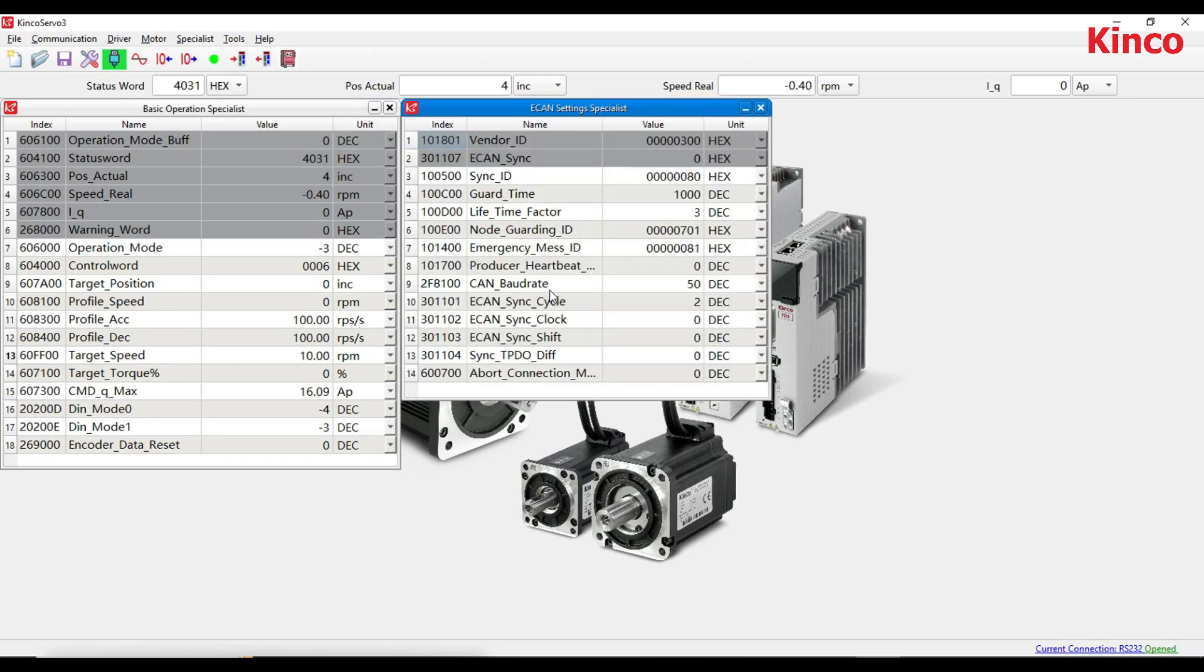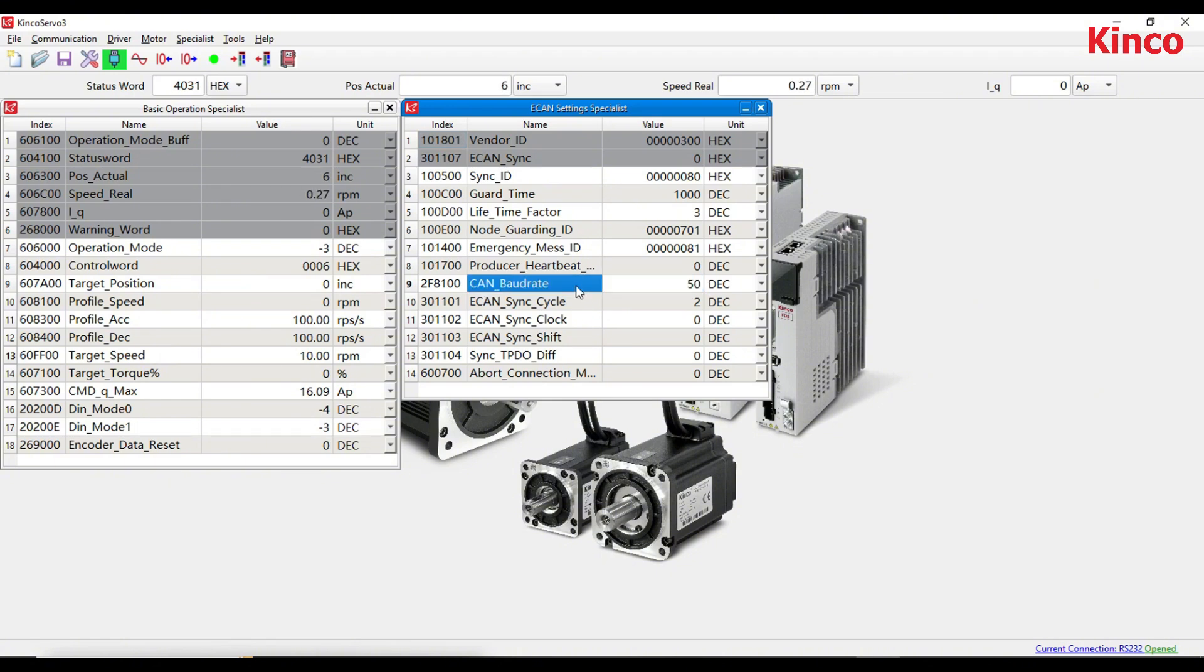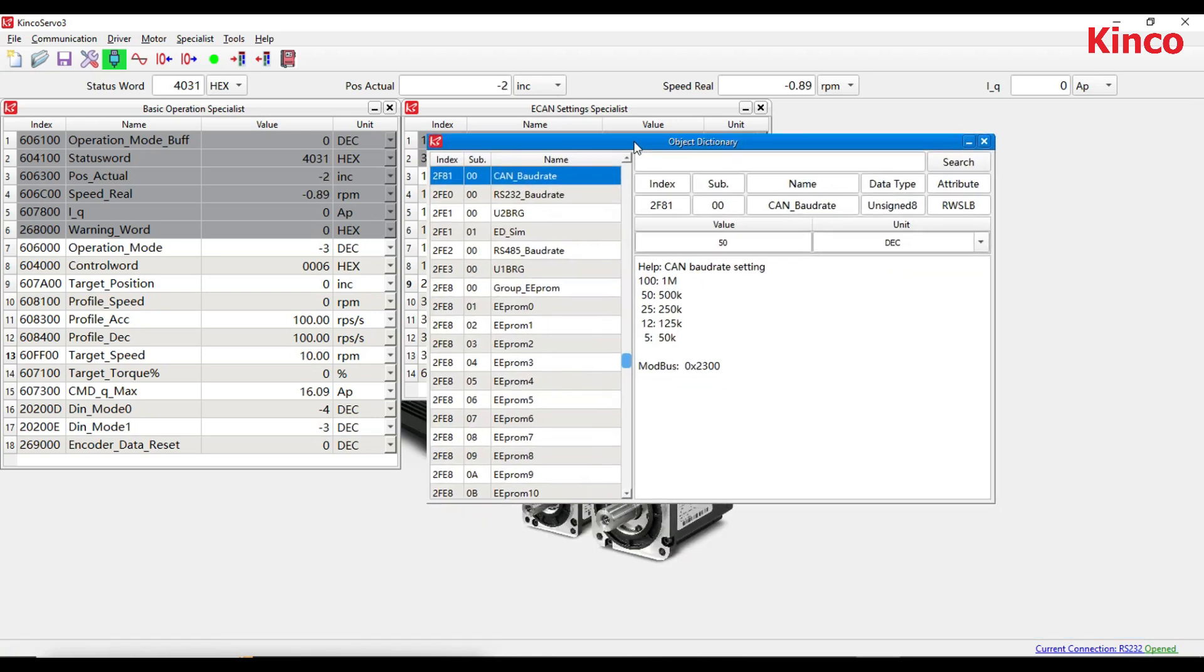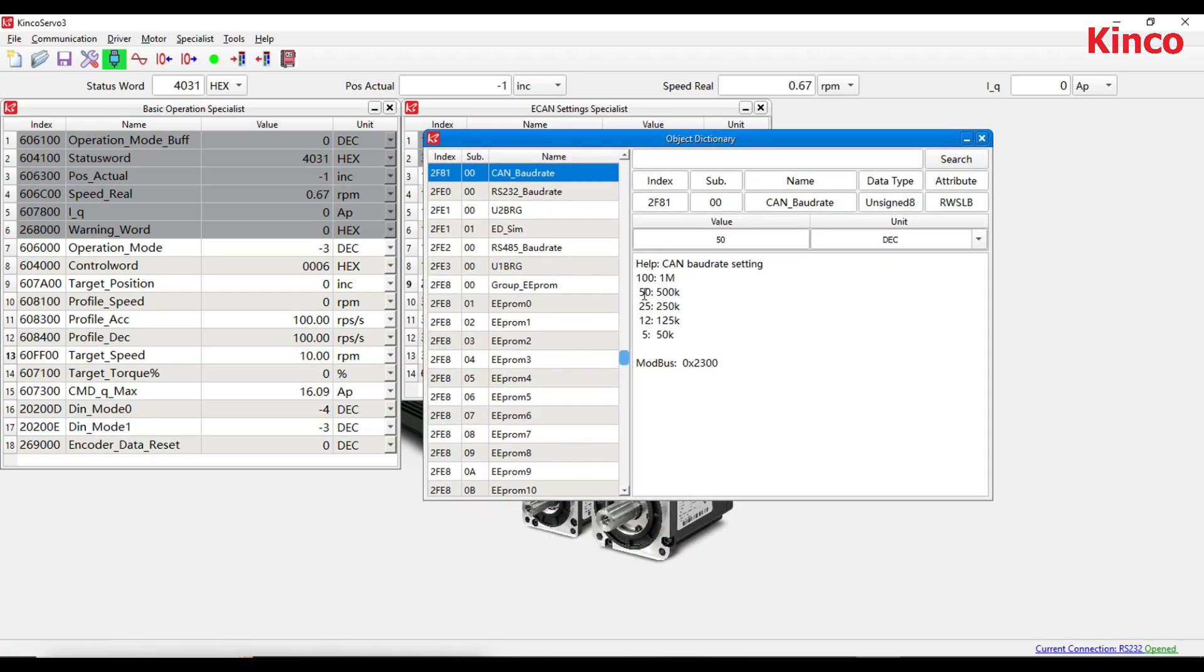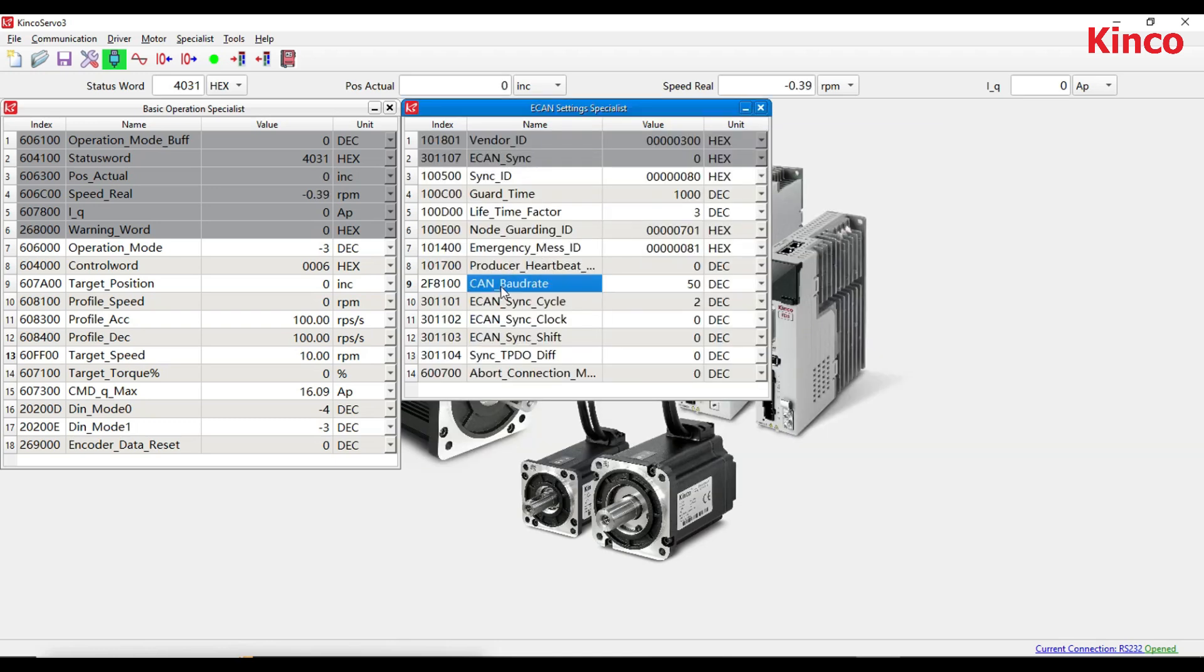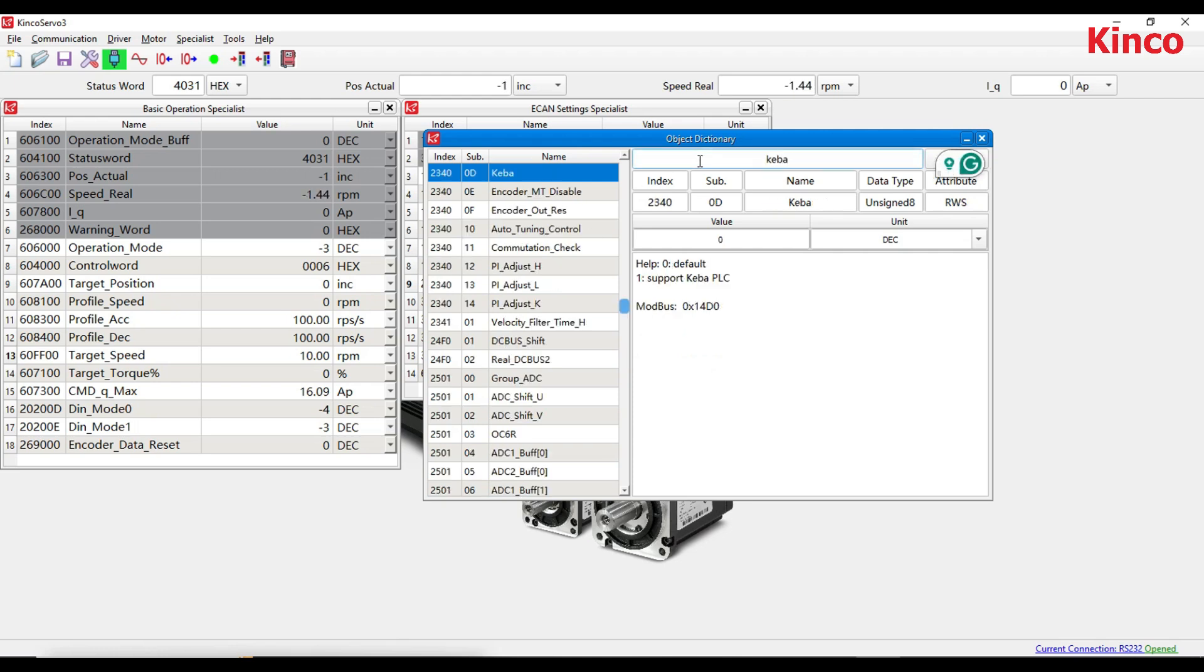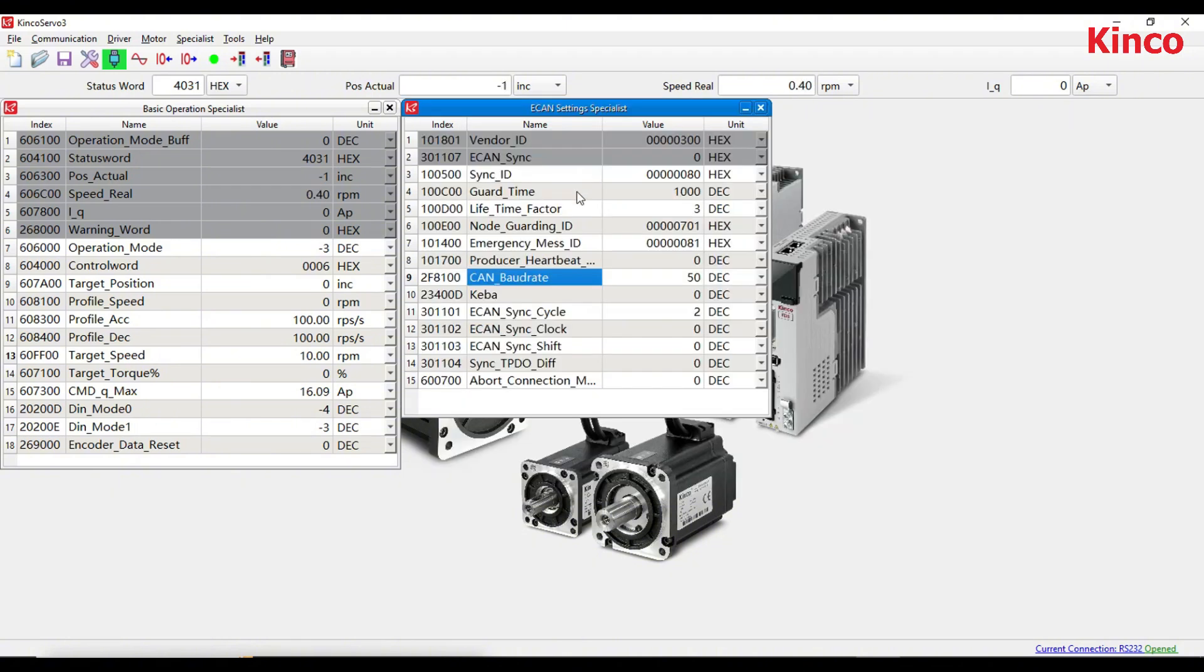Ensure that the baud rate is set to match the baud rate value of the PLC. Open the object dictionary, add a row for KEBA, and set KEBA to 1 for CAN open communication.